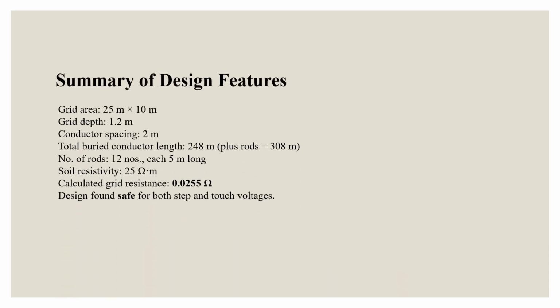From the given data, we can deduce a summary of design features. In this design example, the substation has a grid area of 25 by 10 meters and a grid depth of 1.2 meters. Having conductor spacing of 2 meters, the total buried conductor's length is 248 meters plus rods, which is 308 meters. The calculated grid resistance is 0.0255 ohms. This value is excellent and ensures that both step and touch voltages remain within the safe limits.